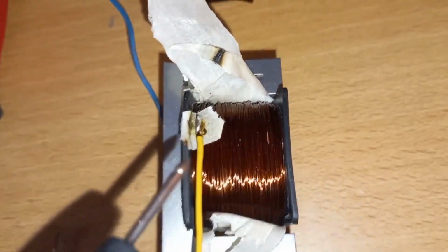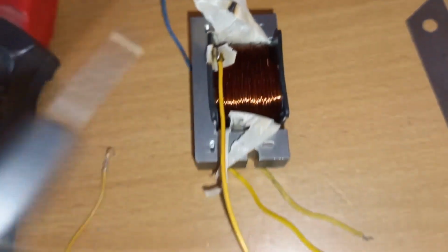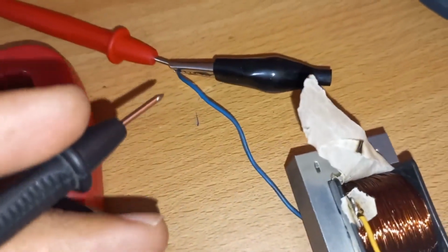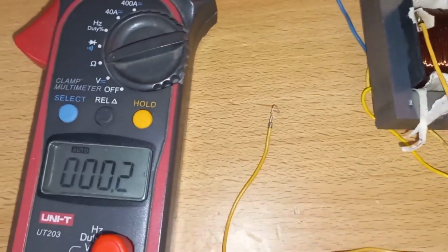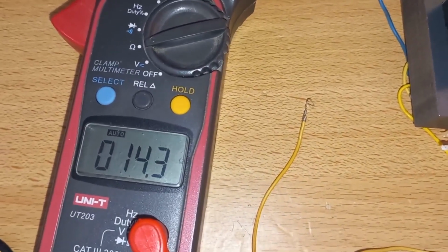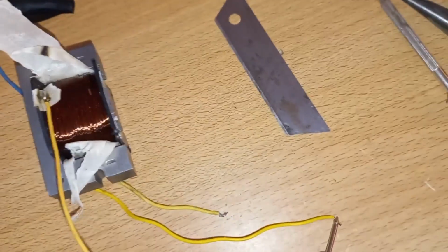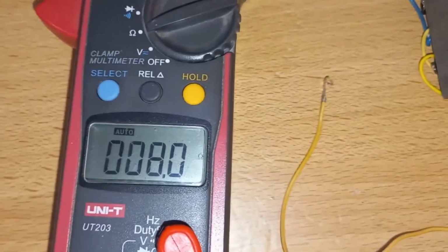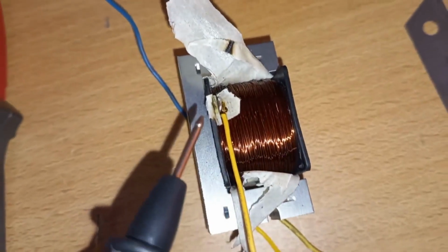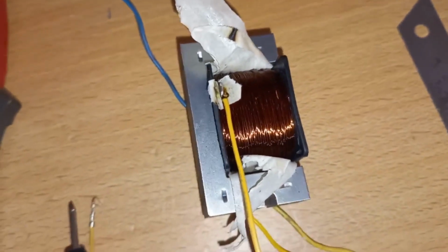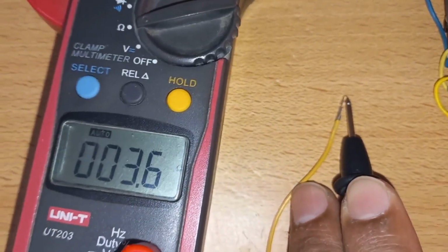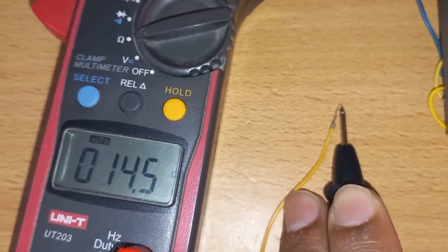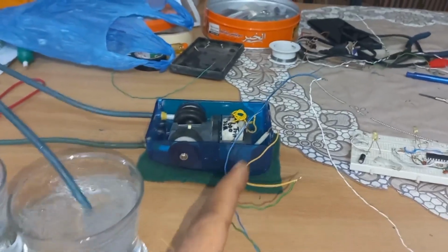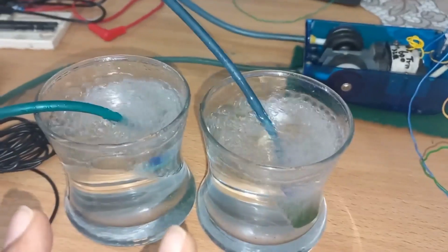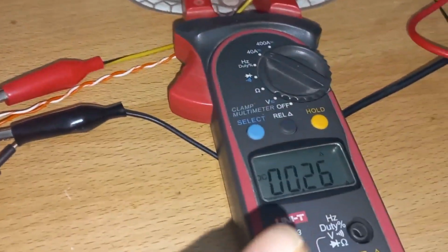Thanks God, I found a wire point here with close resistance. This blue wire is at the red wire of the meter, and this black, if I connect at the first point, gives 14 ohm resistance, 14.3, this was my first loop. The second one here was giving 17 ohm, then I found this point and connected this yellow wire. At this point I get 14.8, very close to loop 1, 14.6. After taking out that loop and reconnecting the transformer, the air bubbles are coming out best. At this time the current is 0.26.